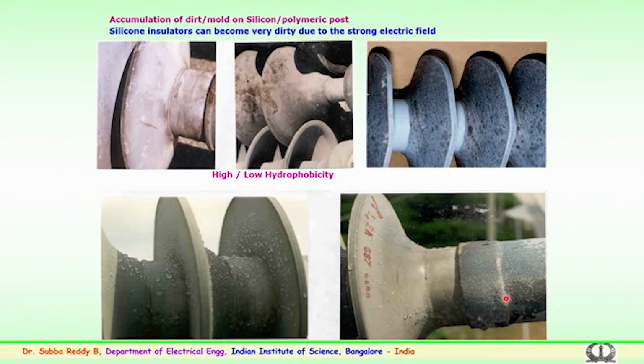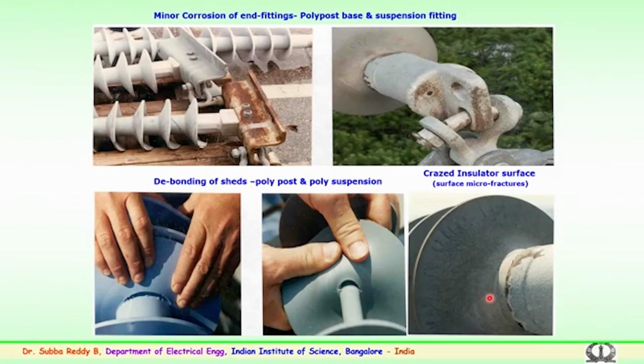So, these are earlier polymers, but some improvements have happened over a period. This again is corrosion of the end fittings of the polymer rod, which could lead to the failure of the insulator string. This is again the hardware or clamps used for the end terminations, which could lead to failure over a period of time. Again, this is a cracked rod, and these are the older generation of polymer insulators, not made by the liquid injection molding machines which are presently used.